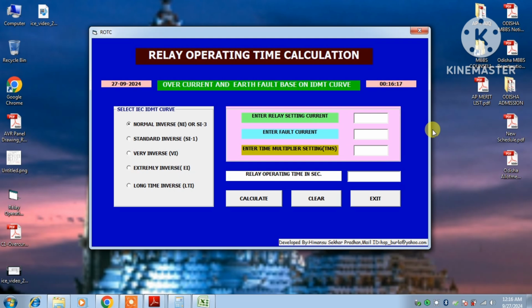After that, the last example I am giving: suppose I take 1 amp, my fault current is 5 times or 6 times, and my TMS is 0.25. If I click normal inverse curve and calculate, it will automatically operate in 959 milliseconds.